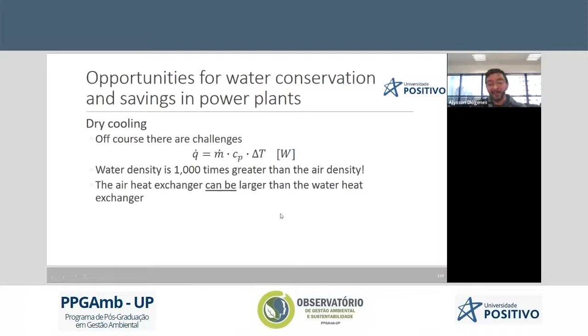The size is like 4 to 6 times bigger than the wet system, and even worse, the cooling system depends on the ambient temperature, and that's a problem. When you've got a summer day in Texas or near a desert, that just doesn't work. I know the vapor is coming around 100 degrees, but you need cold water in the pump.